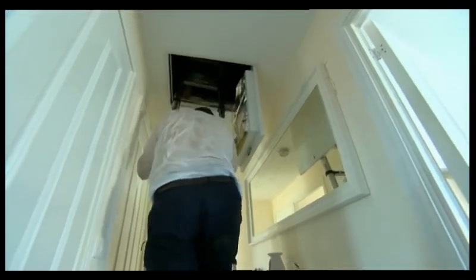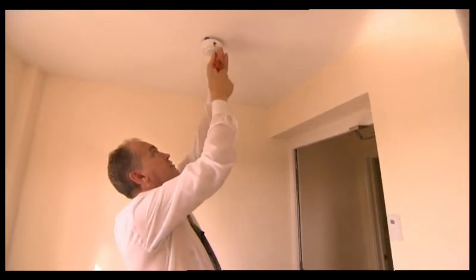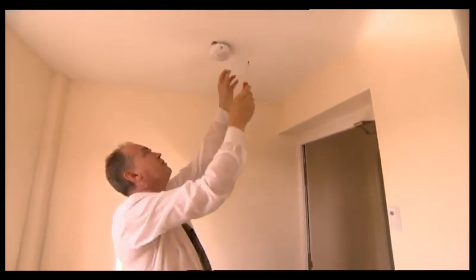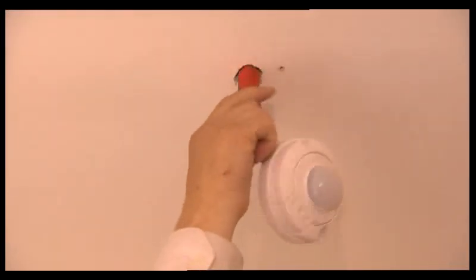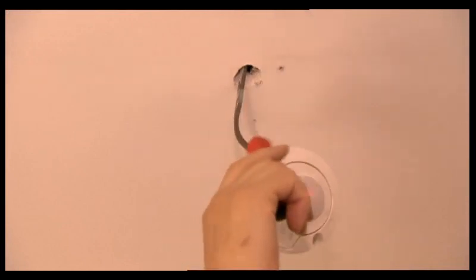Arnold heads downstairs to the stairwell to see if electrical fittings in the ceiling there have been fire stopped. Well, I can see straight through into the ceiling. That hasn't been fire stopped. Arnold reports back to Adam. The plasterboard hasn't been sealed properly on the walls, so I can see gaps between them, so fire in the common part can come up into the loft. It needs to be fire stopped, and a fire break between the 2 areas. They've partially built one, so they know it needed to be in there, otherwise they wouldn't have built that over height blockwork, but they never did it properly.